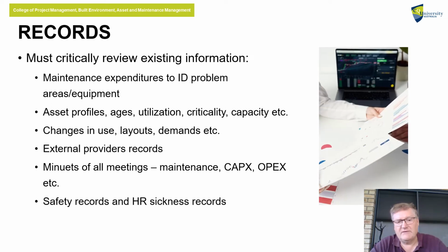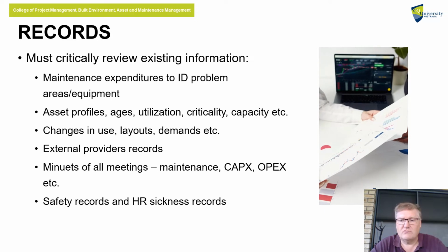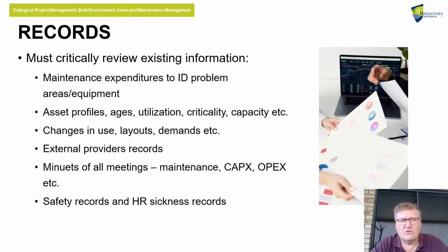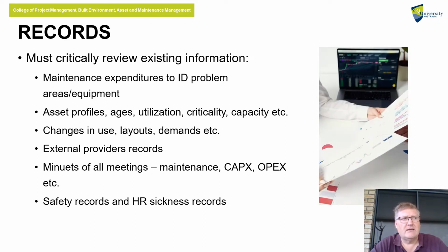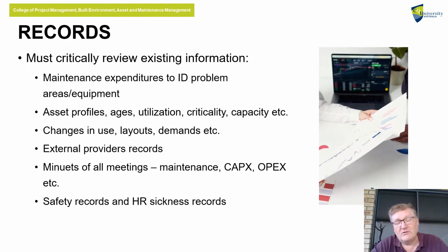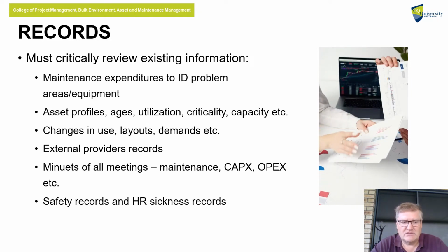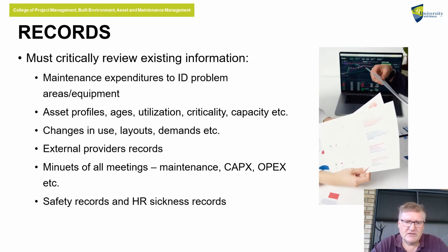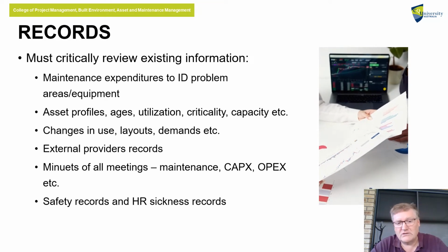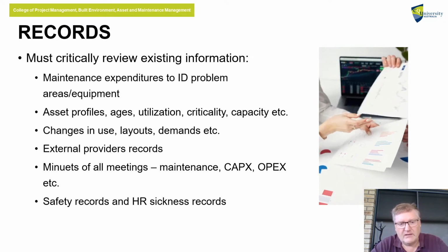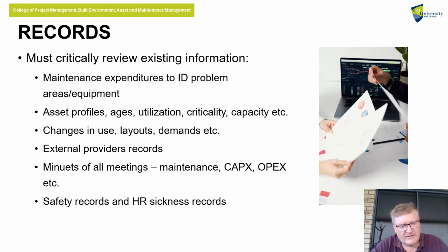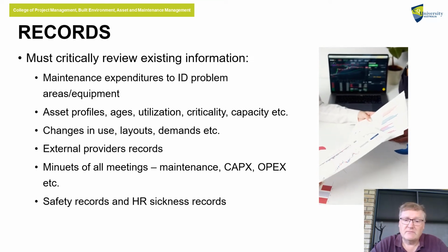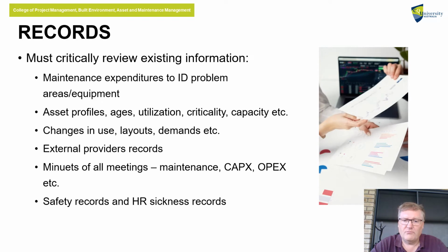And don't forget to look at your safety records and your human relations records. The reason I put HR sickness records in is because when I was responsible for the Queensland court system, we had a problem with, I can only call it sick building syndrome in some of the sites, some of the bigger ones actually, but it wasn't the whole building. When we started to analyse, people were complaining, so I looked at the sickness records and identified them on the plans to see if there were clusters, and there were clusters. There were clusters of people being off more than anyone else.